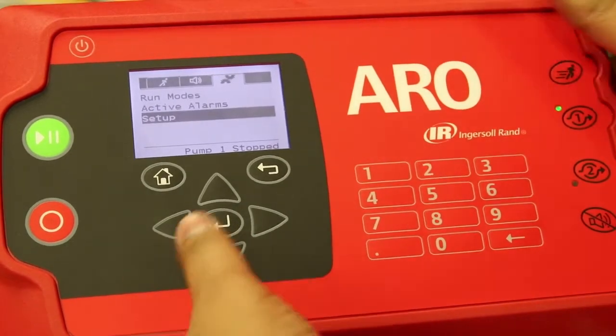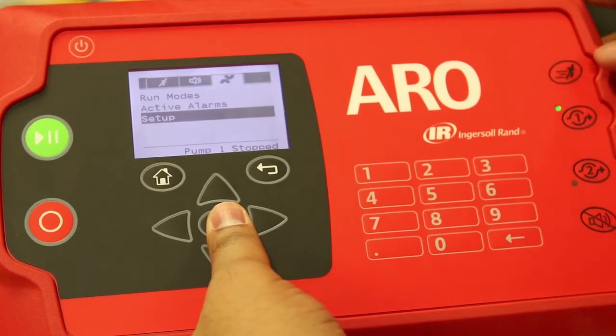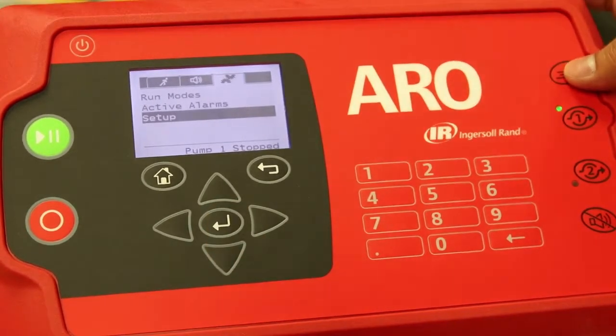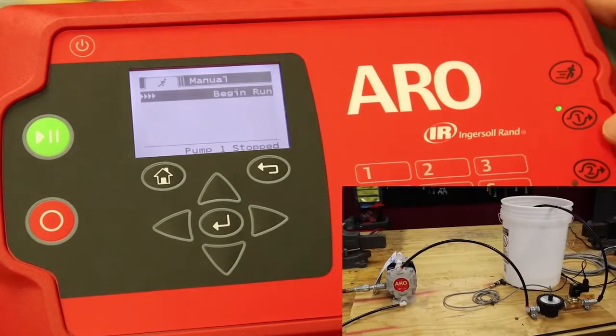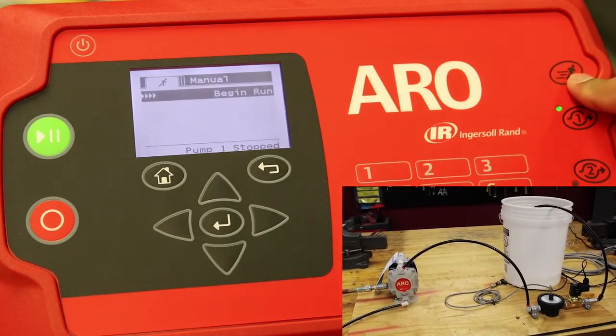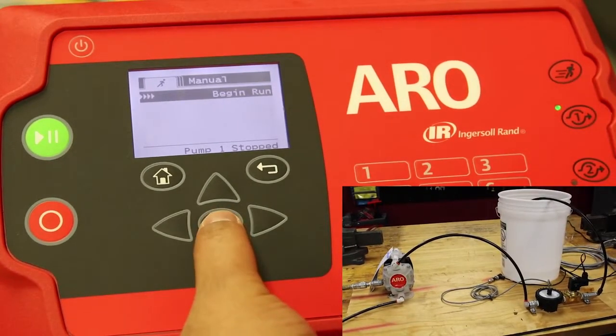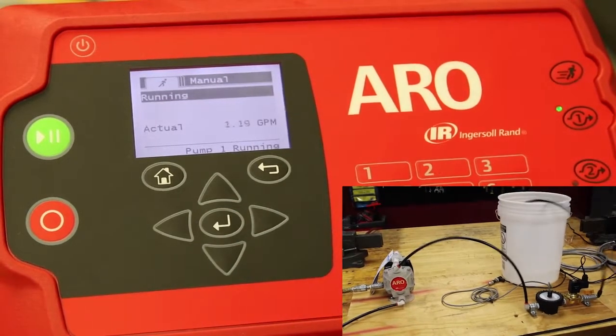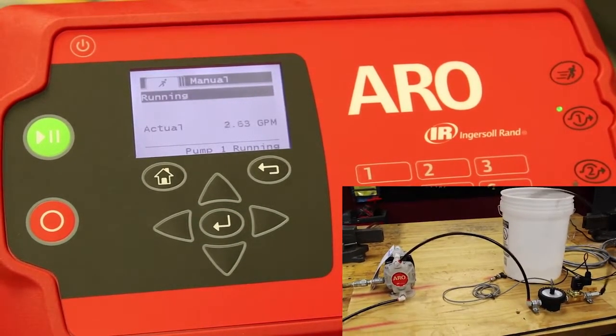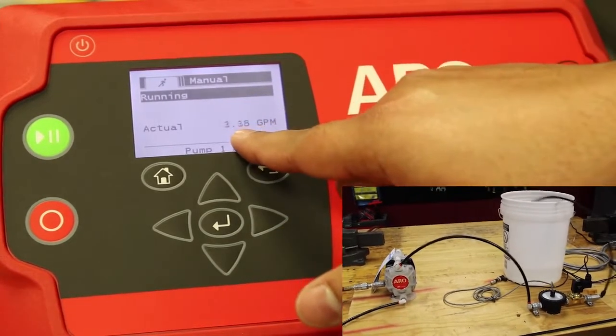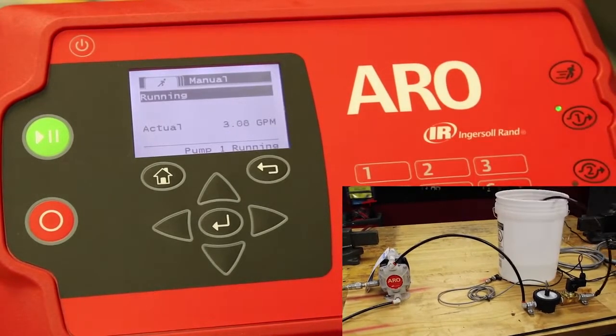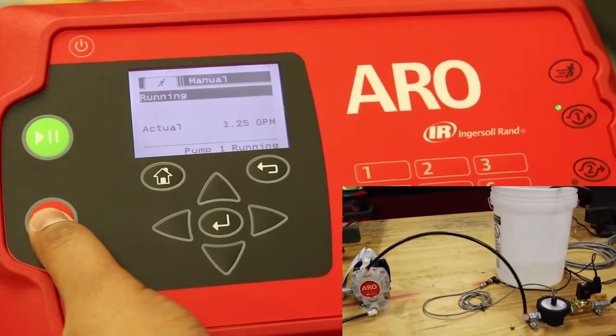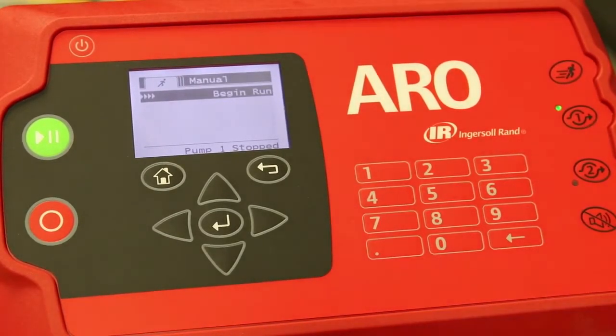We'll now take a test run of how to get the flow meter working and the solenoid valve open. Easiest way to complete an operation in terms of transferring a batch from one tank to the other would require us to go into the quick start menu, and we'd launch the quick start menu with this button. We can now begin the process by hitting begin run, and as you can notice, you see that the solenoid valve is open, and we can see the readout of the actual flow through the flow meter. And to stop the solenoid or close the solenoid valve, we hit stop. And that's the easiest way to get started with a flow meter and a solenoid valve combination with the ARO controller.